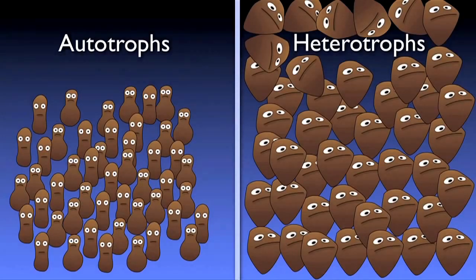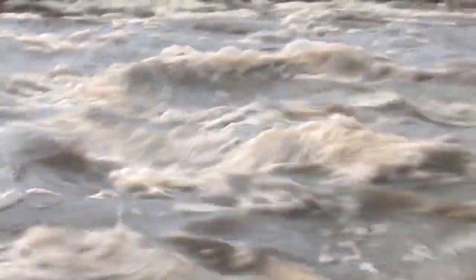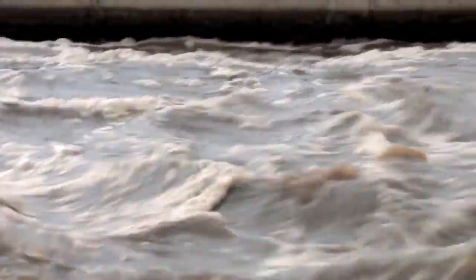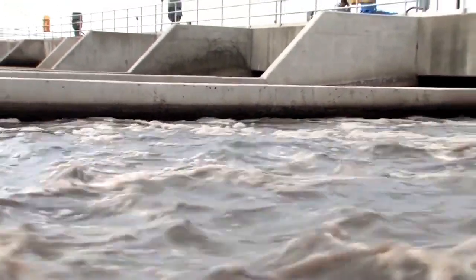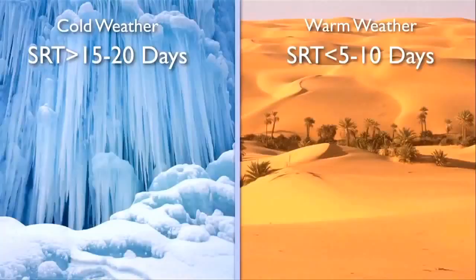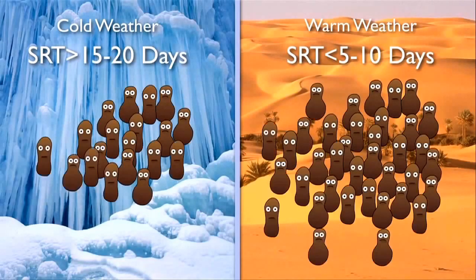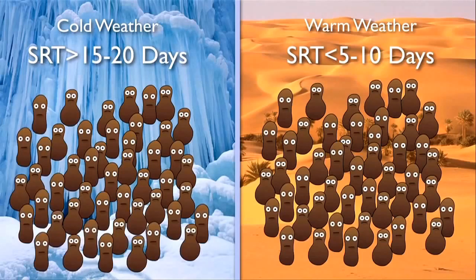The nitrifiers dictate the SRT in nitrogen-reducing plants. How fast nitrifiers grow depends on the temperature of the wastewater and the amount of dissolved oxygen present. If nitrifiers aren't allowed enough time to thrive, you run the risk of accidentally wasting them out of the system entirely and losing nitrification. Higher temperatures and DO concentrations mean faster growth; colder temperatures and lower DO concentrations mean slower growth.